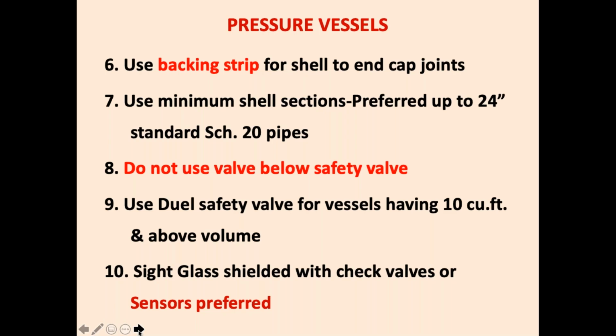If you want to use it, some customers insist on a stop valve, then keep the valve fully open, remove the handle, and the handle should be kept somewhere under lock and key, much away, so that the operator does not fiddle with the handle. Use dual safety valves. Side glass should be with check valves and with sensors preferred.